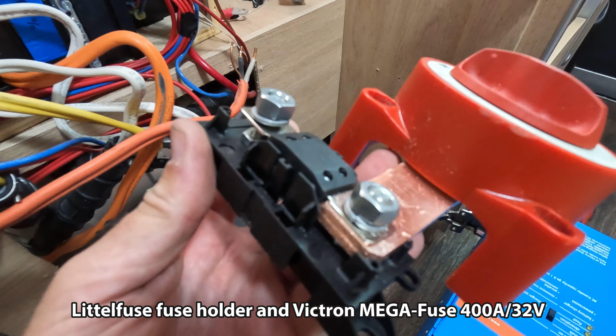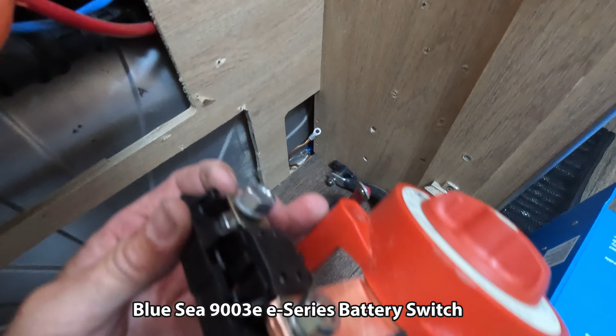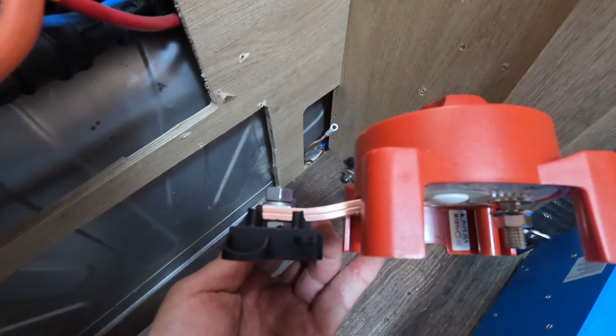I had to replace the fuse from the last inverter, which was 150 amp. The Victron MultiPlus requires a 400 amp fuse. So to keep it as tight as possible, I went from the on-off switch by copper bars, 1/8 inch. I did 2 of them, and bent them slightly so the fuse holder would be flush against the wall.